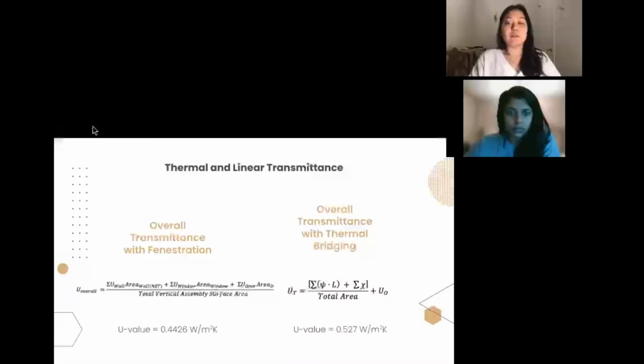The overall building envelope transmittance was also analyzed using two equations provided by Morrison Hershfield in their thermal bridging guide, which is shown on screen. The overall transmittance of the building envelope, including the fenestration assembly, was found to be 0.4426, so approximately an overall RSI of 2.259. For the overall transmittance, including the effects of thermal bridging, the result was a U-factor of 0.527. These values are unfortunately higher than what we would have liked, but it is important to note that a lot of the data regarding the assemblies was taken from the thermal bridging guide for this specific analysis. And while the data is precise in practice, it is not 100% representative of our designed assemblies.